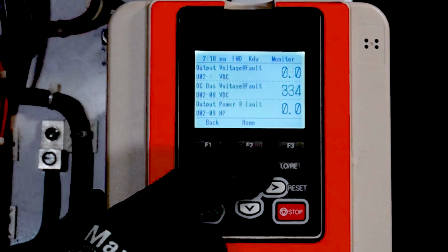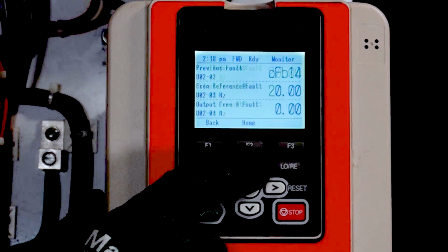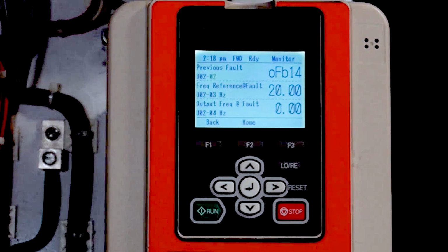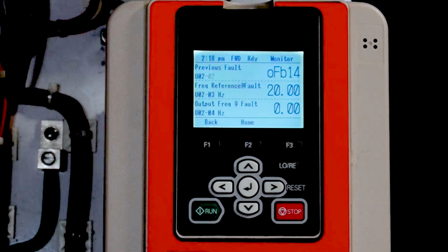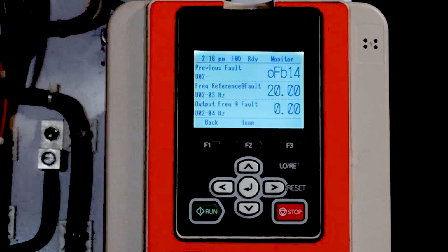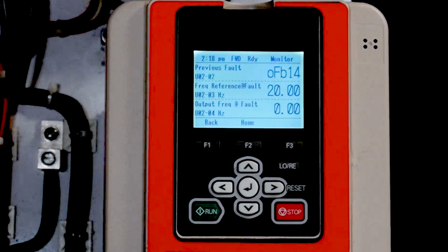And again, you're noticing I'm wearing a glove when doing this. I probably would say this may be compatible with an arc flash glove. I will attempt to duplicate that at another time. I'll put my arc flash gloves on and see if we're able to manipulate these keys. But they're very easy. You can feel them. You know when you've pressed them, that type of thing.